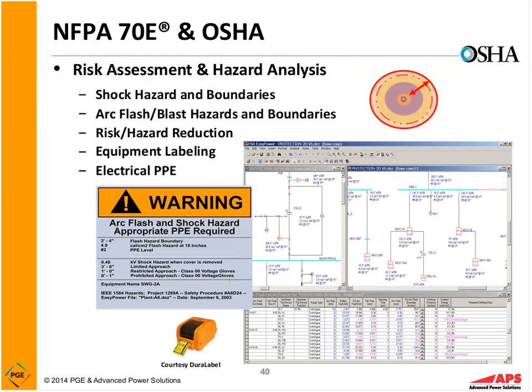So when we look at this, we also need to look at the shock and arc flash boundaries. We don't have time to go into those today, but in other words, how close can I get? At what point does the PPE have to go on to avoid shock? At what point does the PPE have to go on to avoid injury from arc flash? So we need to look at shock hazards and their boundaries, arc flash hazards and their boundaries. We need to look at risk and hazard reduction, equipment labeling so they understand the hazards and how to read the labels, and how to pick their PPE properly. So these are all parts of the risk assessment.